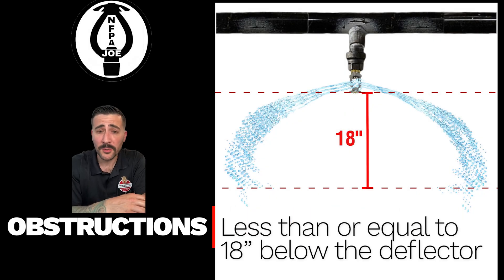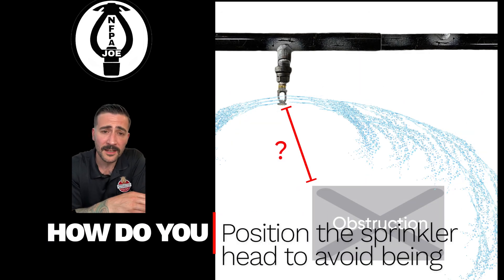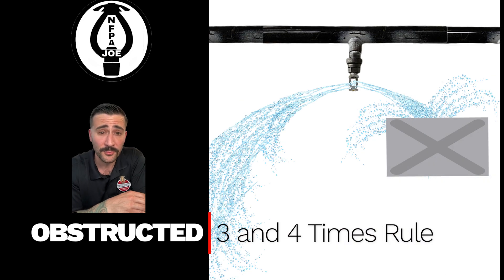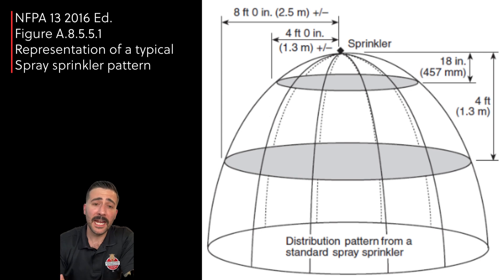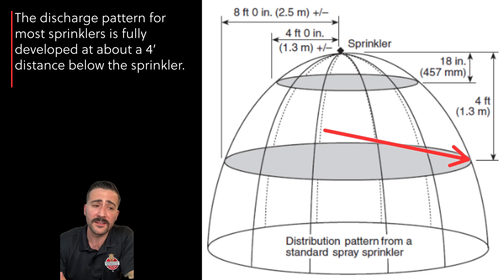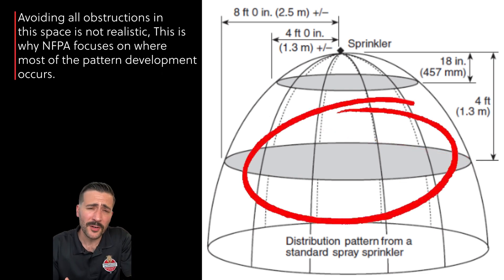Obstructions less than or equal to 18 inches below the sprinkler deflector — how do you position the sprinkler head to avoid being obstructed? You need to learn the three and the four times rule. This is NFPA 13's representation of a typical spray sprinkler pattern. The discharge pattern for most sprinklers is fully developed at about a four-foot distance below the sprinkler. Avoiding all obstructions in this space is not realistic.